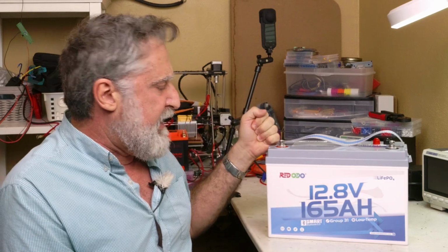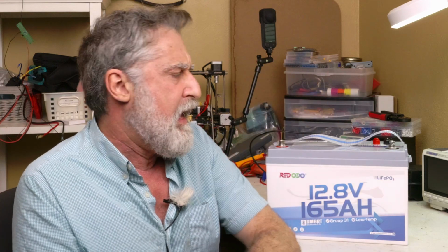It's a digital BMS, and quite often they shut right down at that number. This does have some tolerance built in, so for 1 second you could have 800 amps plus, which is good for starting induction motors on your inverter AC loads, and I think it's 5 seconds at a little bit above 500 amps.